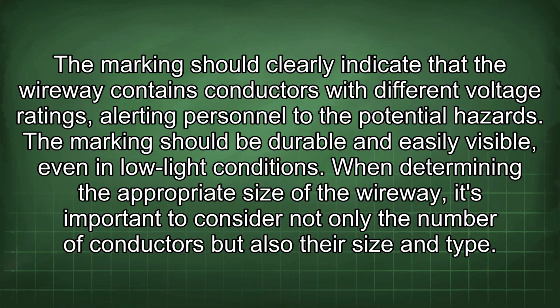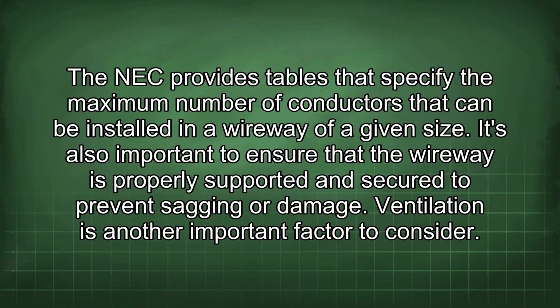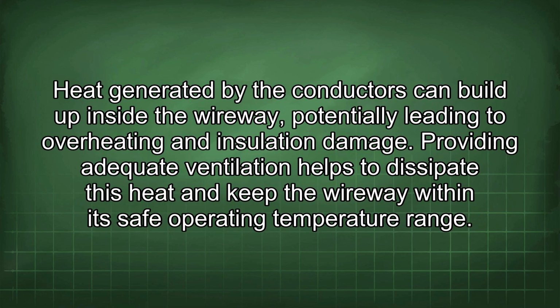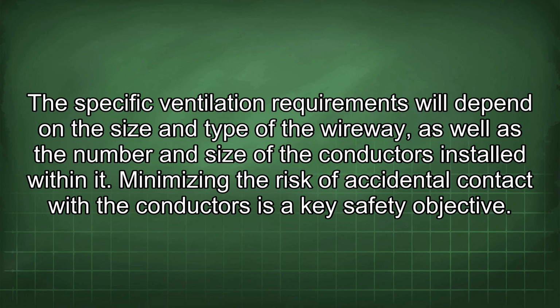When determining the appropriate size of the wireway, it's important to consider not only the number of conductors but also the size and type. The NEC provides tables that specify the maximum number of conductors that can be installed in a wireway of a given size. It's also important to ensure that the wireway is properly supported and secured to prevent sagging or damage. Ventilation is another important factor to consider. Heat generated by the conductors can build up inside the wireway, potentially leading to overheating and insulation damage. Providing adequate ventilation helps to dissipate this heat and keep the wireway within its safe operating temperature range. The specific ventilation requirements will depend on the size and type of the wireway, as well as the number and size of the conductors installed within it.